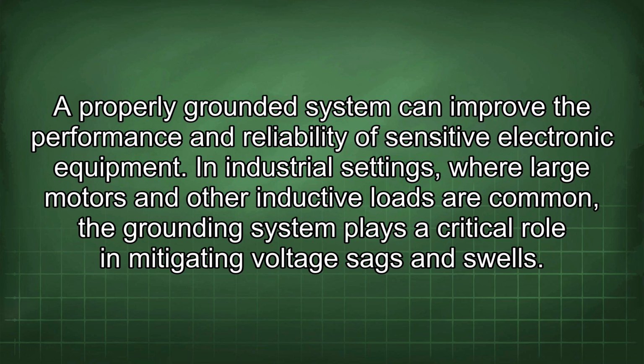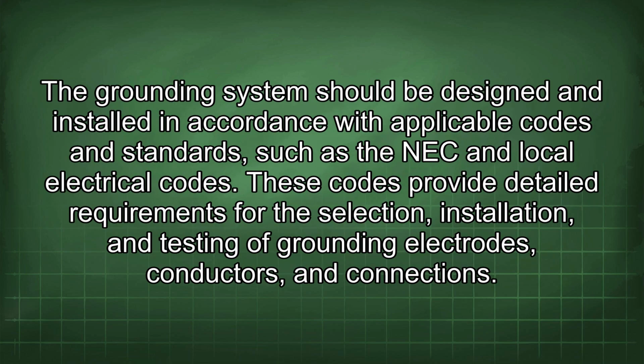In industrial settings where large motors and other inductive loads are common, the grounding system plays a critical role in mitigating voltage sags and swells. The grounding system should be designed and installed in accordance with applicable codes and standards, such as the NEC and local electrical codes. These codes provide detailed requirements for the selection, installation, and testing of grounding electrodes, conductors, and connections.